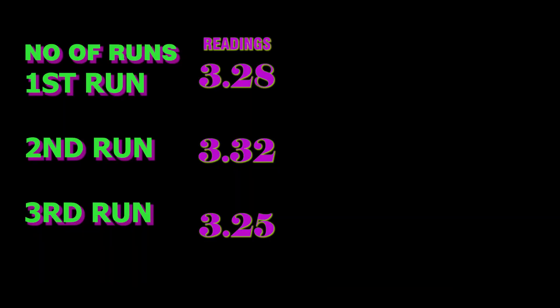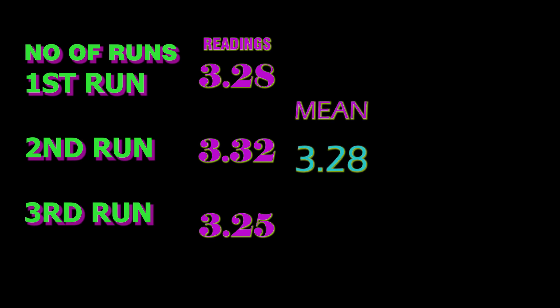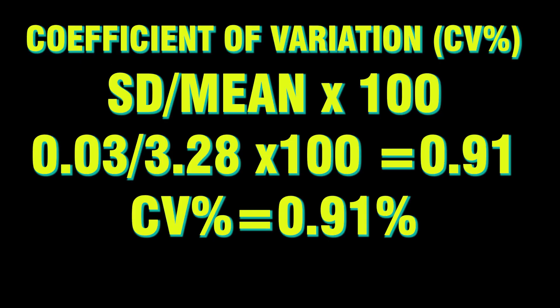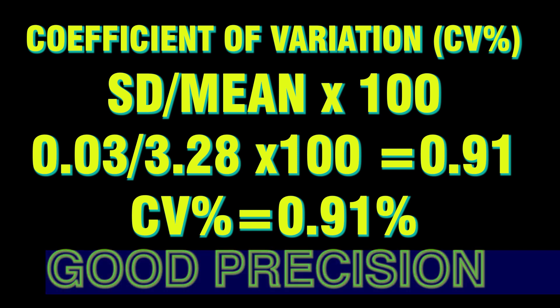How does the instrument check the coefficient of variation percentage? In example one, there are three OD readings: 3.28, 3.32, and 3.25. The mean for the three readings is 3.28, the SD value is 0.03, and dividing SD by the mean gives a coefficient of variation percentage of 0.91%, which is very good.